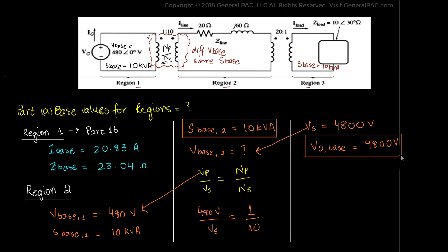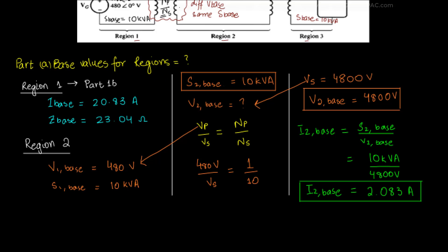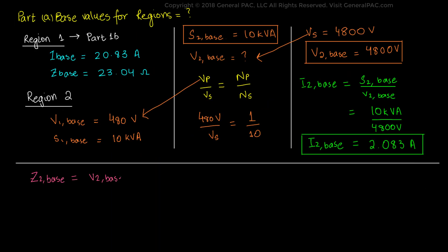Now we can easily calculate the other base values for Region 2. I2-base equals S2-base divided by V2-base, which is 10kVA divided by 4800V, which equals 2.083A. Z2-base equals V2-base divided by I2-base, which is 4800V divided by 2.083A, which equals 2,304 ohms.